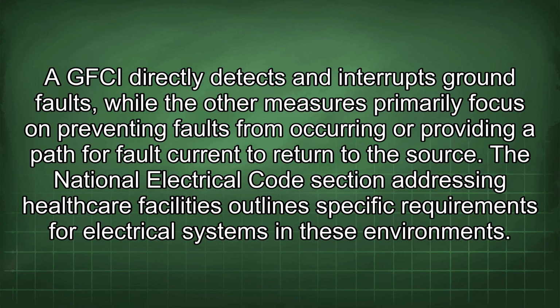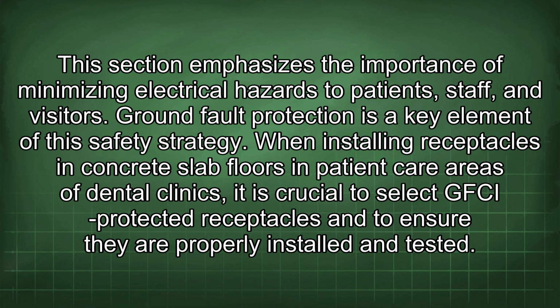The National Electrical Code section addressing healthcare facilities outlines specific requirements for electrical systems in these environments. This section emphasizes the importance of minimizing electrical hazards to patients, staff, and visitors. Ground fault protection is a key element of this safety strategy. When installing receptacles in concrete slab floors in patient care areas of dental clinics, it is crucial to select GFCI-protected receptacles and to ensure they are properly installed and tested.